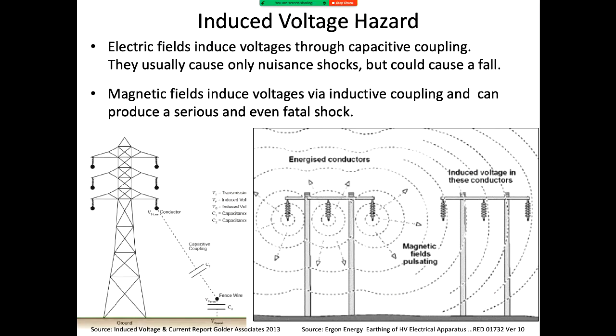Another thing is the induced voltage hazard. There are two kinds. One is capacitive coupling. If you're under a power line and there's a fluorescent tube with a voltage difference, you'll see the tube actually operate. That's a very low current, but it could build up on something like a car, and when you touch it you might jump back. What you don't want is to be up in the air somewhere where you could fall.